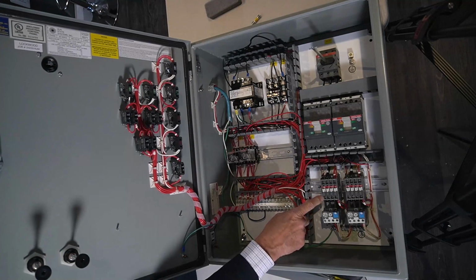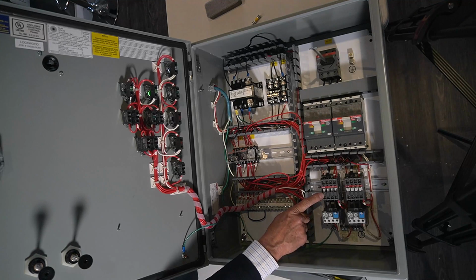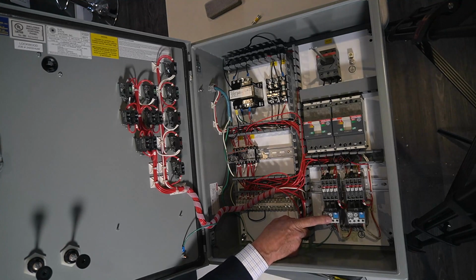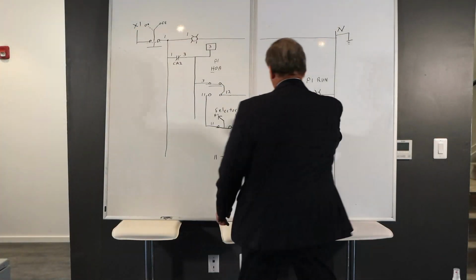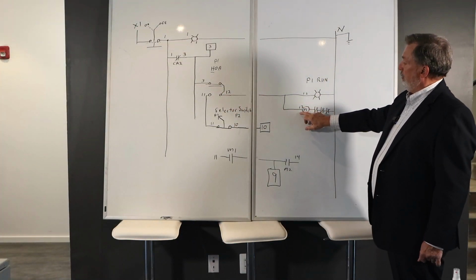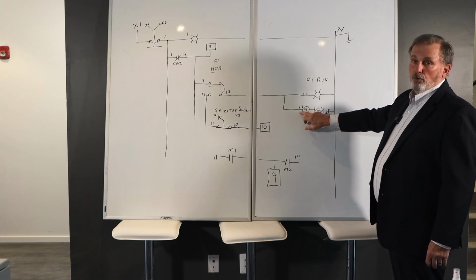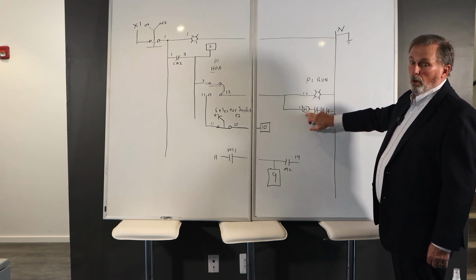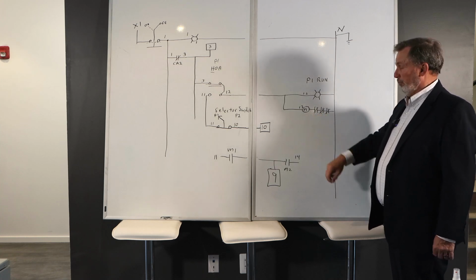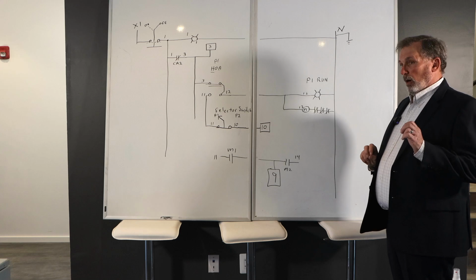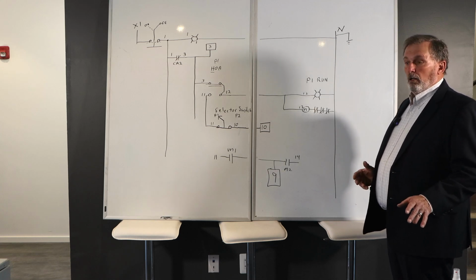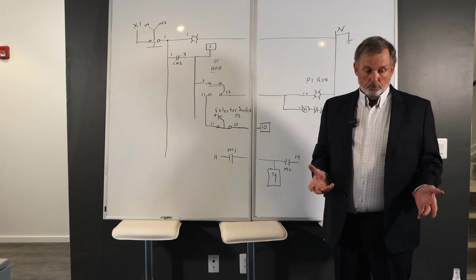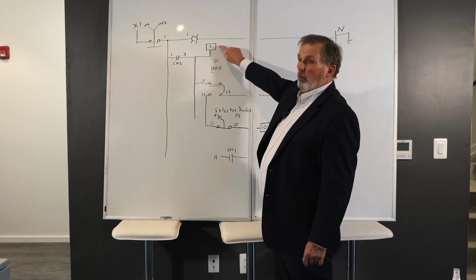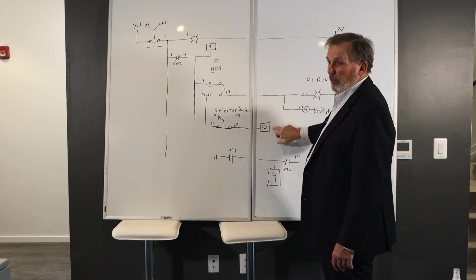Lift the switch, watch number 1. You can see the relay actually pull in while I'm hitting the hand switch. Okay? Relay contact, overload block. These are all my control wires. So, wire number 12, in my ladder diagram, wire number 12 is going to engage the pump motor, the pump starter coil. In automatic, I am only going to go into automatic when I want to have a float switch control the pumps.